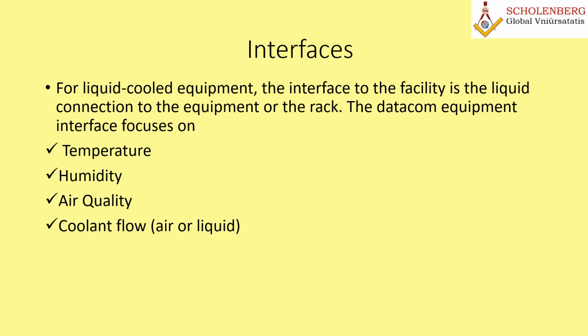Now let's move on to the interfaces. For air-cooled datacom equipment, the primary interface to the facility is the air inlet to the datacom equipment. On the contrary, for liquid-cooled equipment, the interface to the facility is the liquid connection to the equipment or rack. The datacom equipment interface focuses on temperature, humidity, air quality, and coolant flow, whether air or liquid.